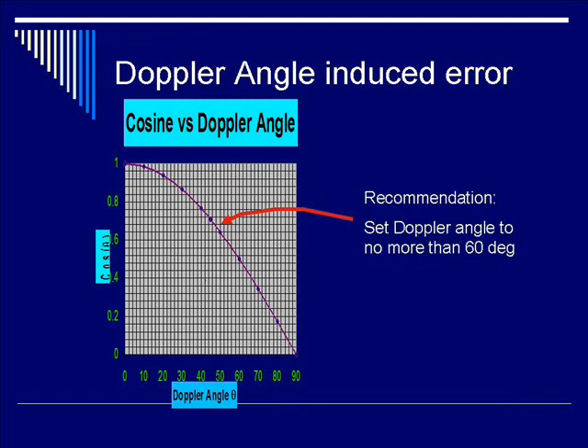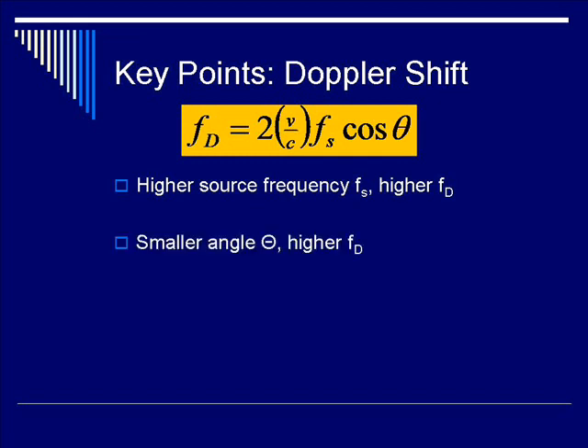In addition, if you measure at 60 degrees or more, the percentage of error as a function of the angle increases dramatically. So despite measuring at less than 60 degrees, you're looking at a minimum of 10 to 20% error in the best case scenarios. As a key point summary: higher source frequency gives a higher shift, a smaller angle gives a higher shift, and higher blood flow velocity also gives a higher shift.